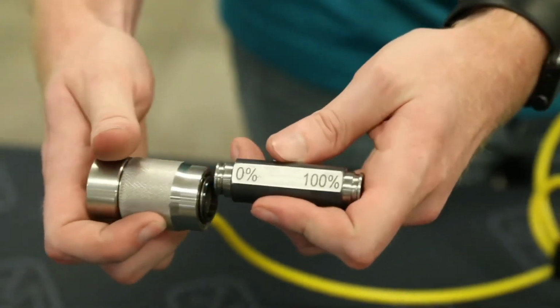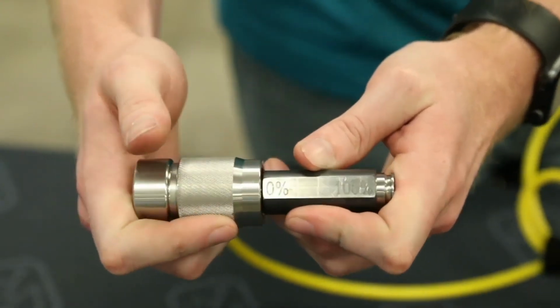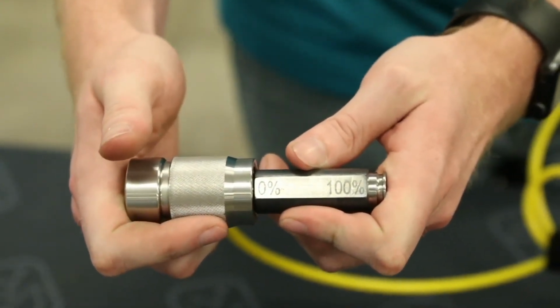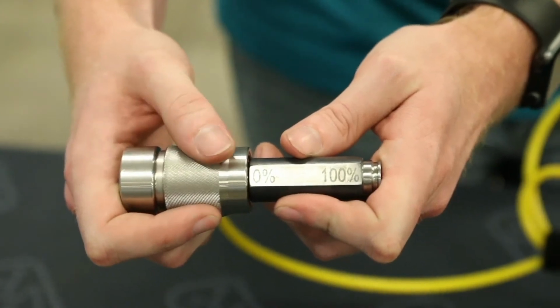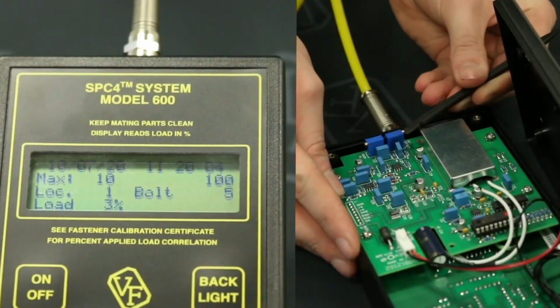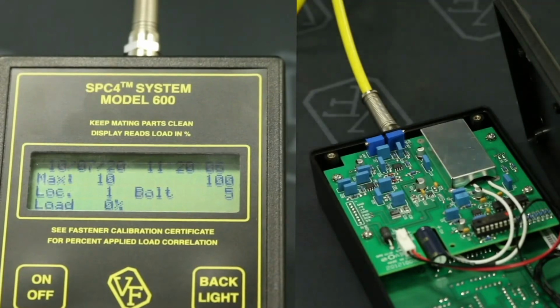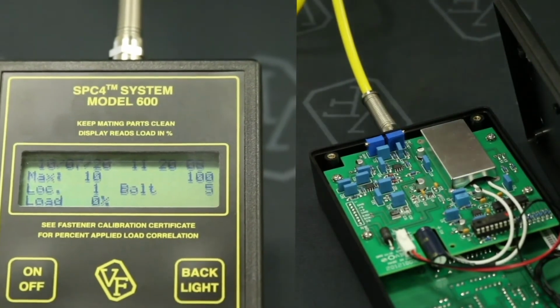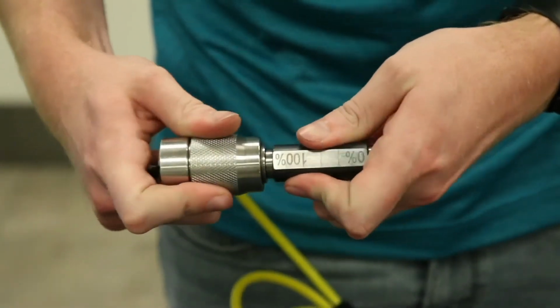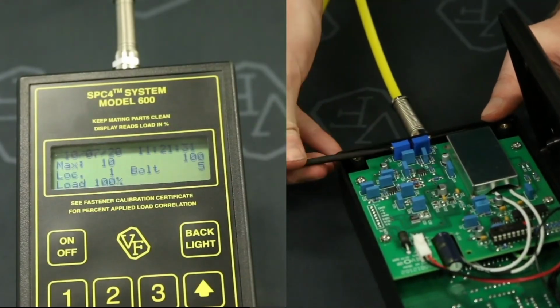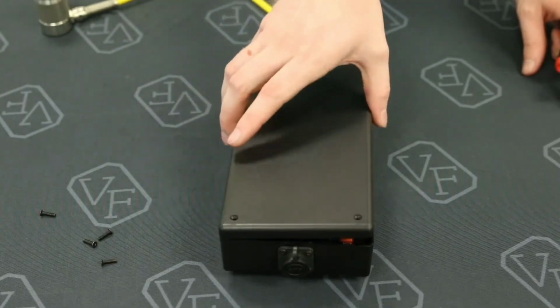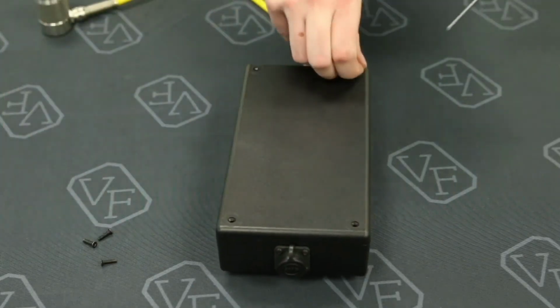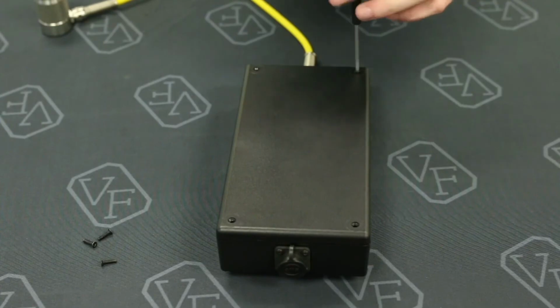With the 600A unit on, attach the 0% end of the calibration gauge to the 600A probe. Adjust the offset potentiometer as necessary until the 600A LCD reads 0%. Remove the calibration gauge and then attach the 100% end of the gauge to the 600A probe. Adjust the gain potentiometer so that the display shows 100%. Perform a final calibration check to confirm proper calibration has been achieved and reattach the rear of the 600A enclosure.